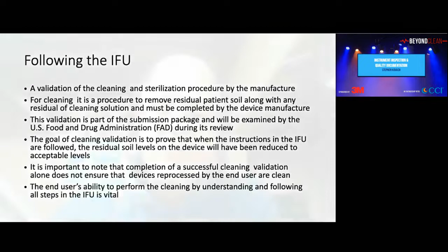That is doing it the right way legally, following their IFU and their times. The goal of cleaning validation is to prove that when the instructions in the IFU are followed, the residual soil level on the device will have been reduced to acceptable levels that have been accepted by the FDA. It's important to note that completion of a successful cleaning validation alone does not ensure that device reprocessing by the end users is clean. The end user's ability to perform the cleaning by understanding and following all the steps in the IFU is vital. Can they follow them?